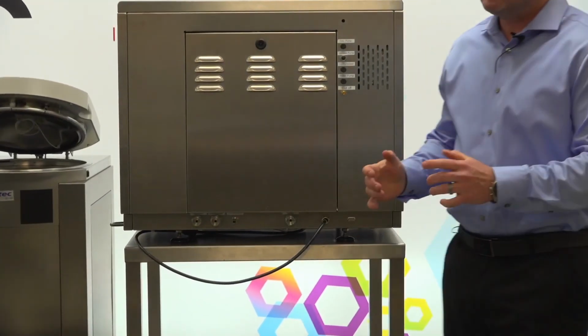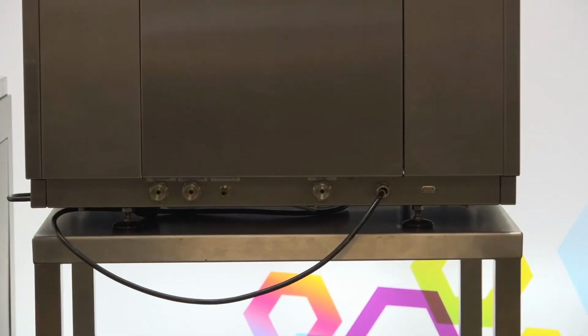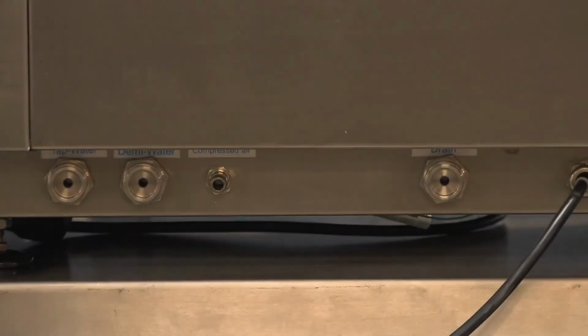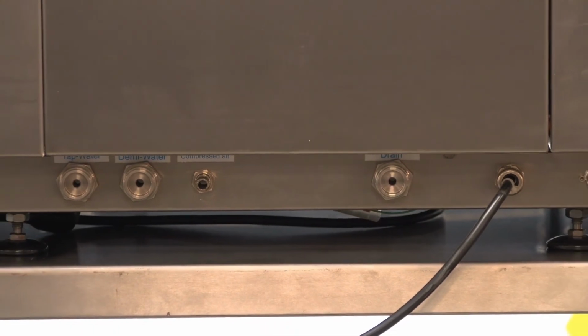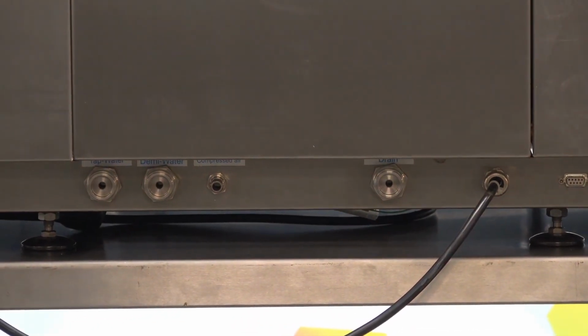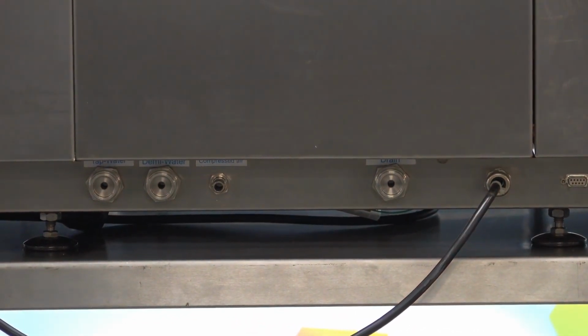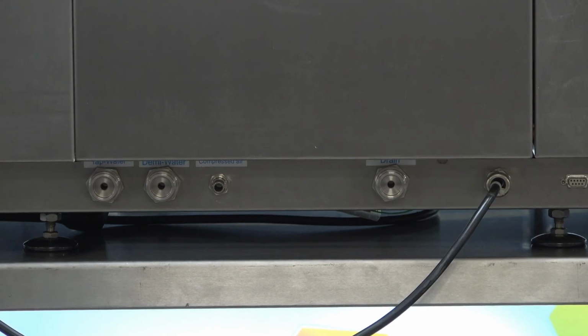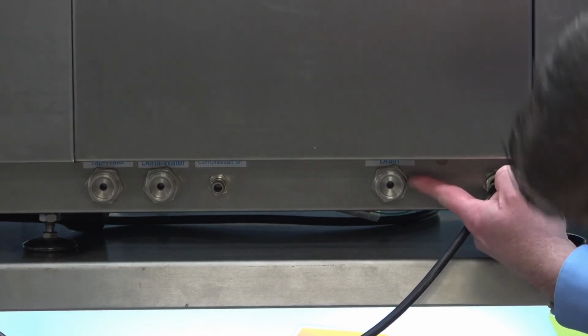So as far as utilities are concerned, we need power. These instruments run on 220 volt power for the most part. Some of our smaller instruments run on a 220 single phase. Most of them run on 220 three phase. It only requires one power attachment. Many other systems are going to require a 110 volt for the operating controls, and then 230 or 220 for your steam generator. We run it off of just one single source of power. So that would be the power requirement. Then the next one we're going to have here is we do need a drain.